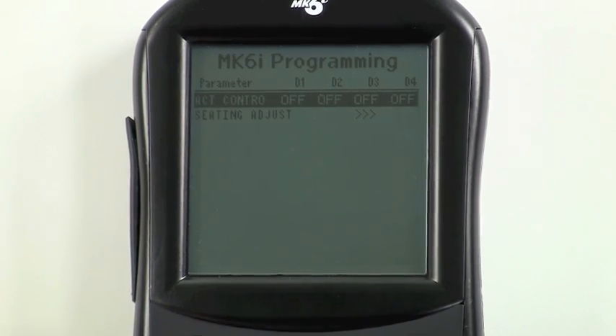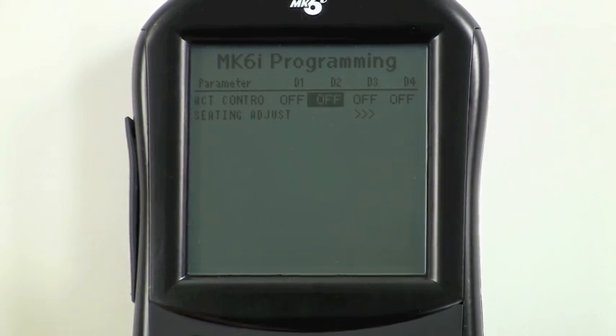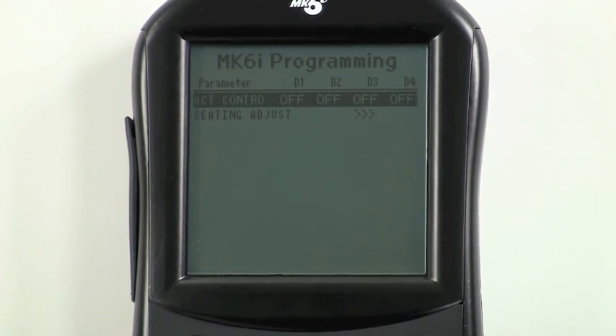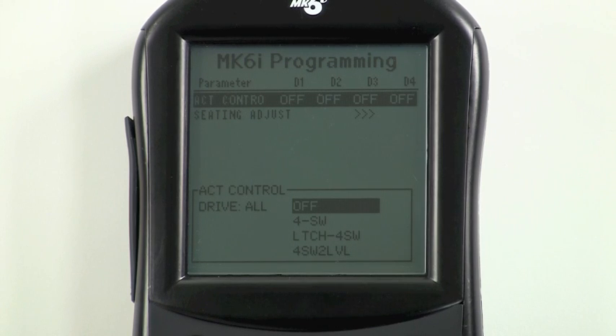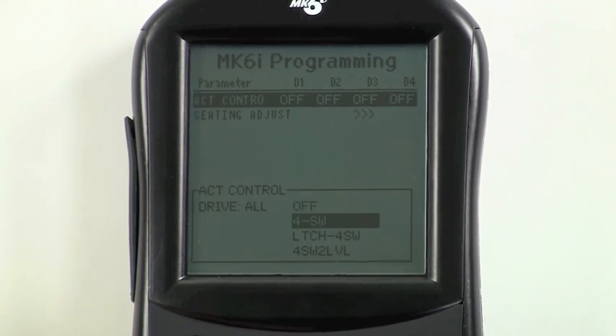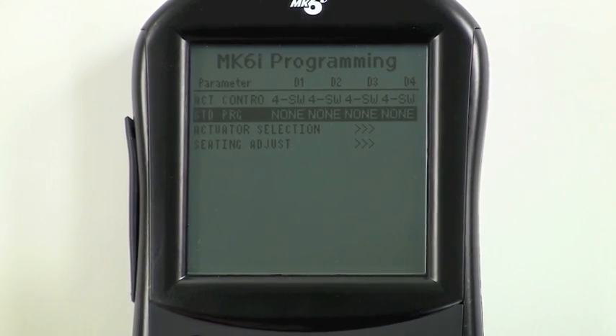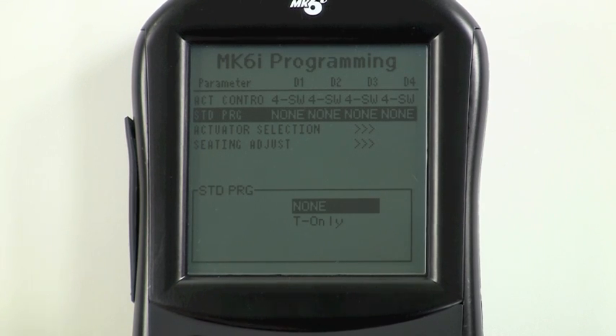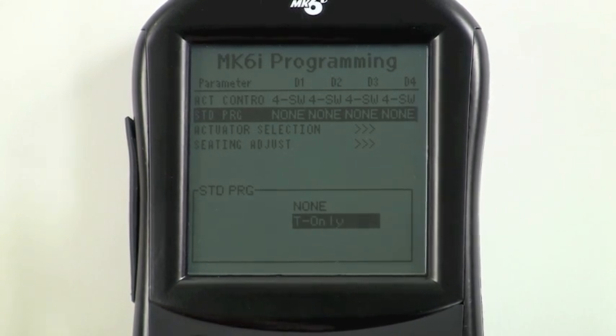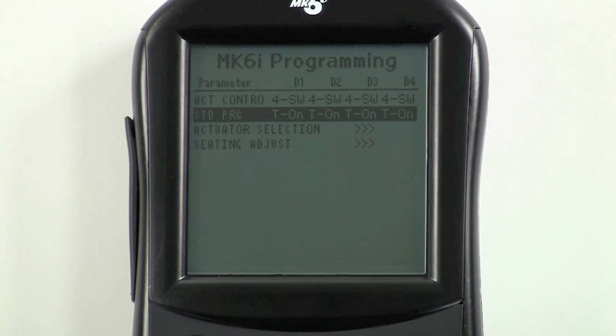Scroll to the desired drive profile, or to set it up in all drives, highlight all four drives and press select. Choose 4-switch and press select again. Scroll down to actuator control standard programs and press select. Choose tilt only and press select. On a tilt only system, the default program uses the forward command for tilt up and the reverse command for tilt down. Left and right driver commands are turned off. If this works, you are done and changes can be saved.